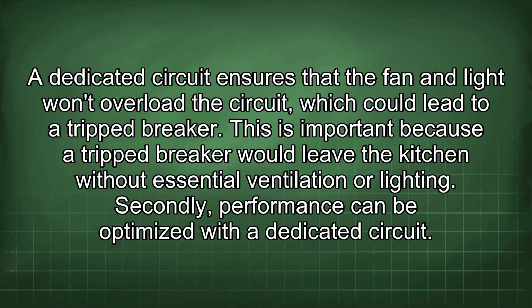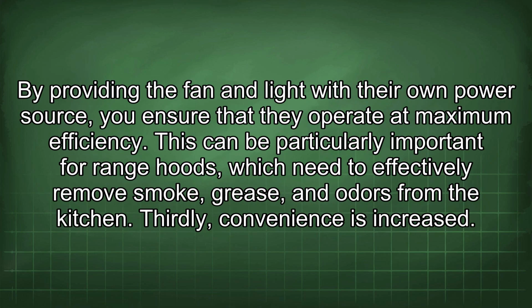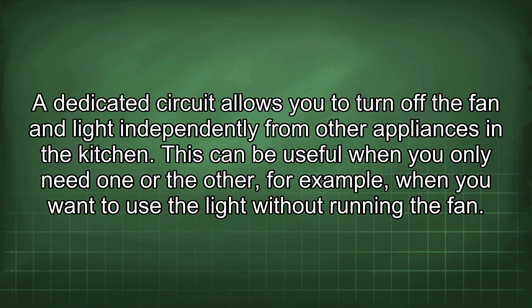Secondly, performance can be optimized with a dedicated circuit. By providing the fan and light with their own power source, you ensure that they operate at maximum efficiency. This can be particularly important for range hoods, which need to effectively remove smoke, grease, and odors from the kitchen. Thirdly, convenience is increased. A dedicated circuit allows you to turn off the fan and light independently from other appliances in the kitchen. This can be useful when you only need one or the other, for example, when you want to use the light without running the fan.